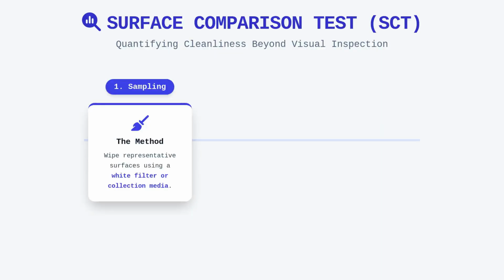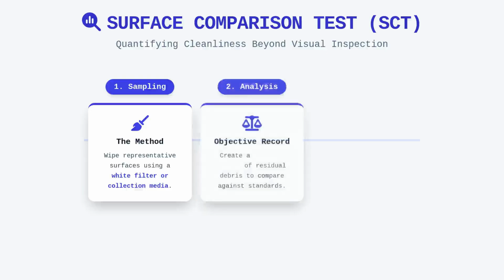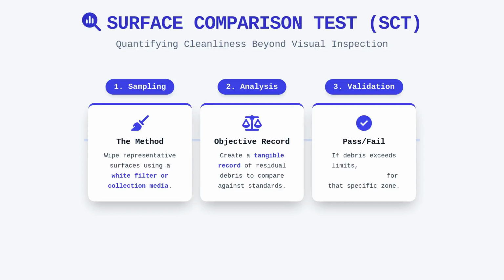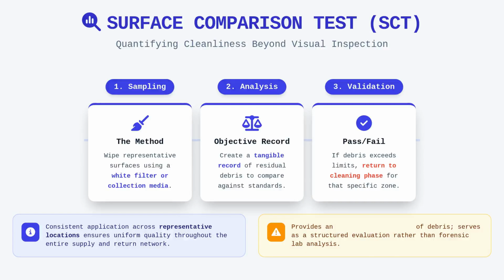One of the more nuanced tools in our arsenal is the surface comparison test, commonly referred to as the SCT. This test provides a structured way to evaluate cleanliness when visual inspection alone might be subjective or difficult to quantify. By using a white filter or a collection media to wipe a representative surface, you create a tangible record of the cleanliness that can be compared against a standard. It is not necessarily a laboratory-grade forensic analysis, but it provides an objective indication of the residual debris levels remaining on a surface after your agitation and vacuuming. If the test results indicate accumulated debris beyond the acceptance limits, you must return to the cleaning phase for that specific zone. This process should be applied consistently across different representative locations within the system to ensure that your cleaning quality is uniform throughout the entire supply and return air network.